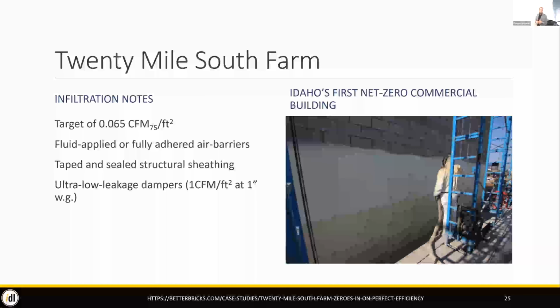In terms of infiltration, they tried to meet the passive house standard, with a target of 0.065 CFM per square foot, compared to the current code of 0.4. So this is 6 times tighter than Idaho's code. They achieved that with fluid-applied, fully adhered air barriers, taping and sealing all the structural sheathing, and specifying super low leakage dampers on all the mechanical equipment so air isn't just passing around all those metal pins.